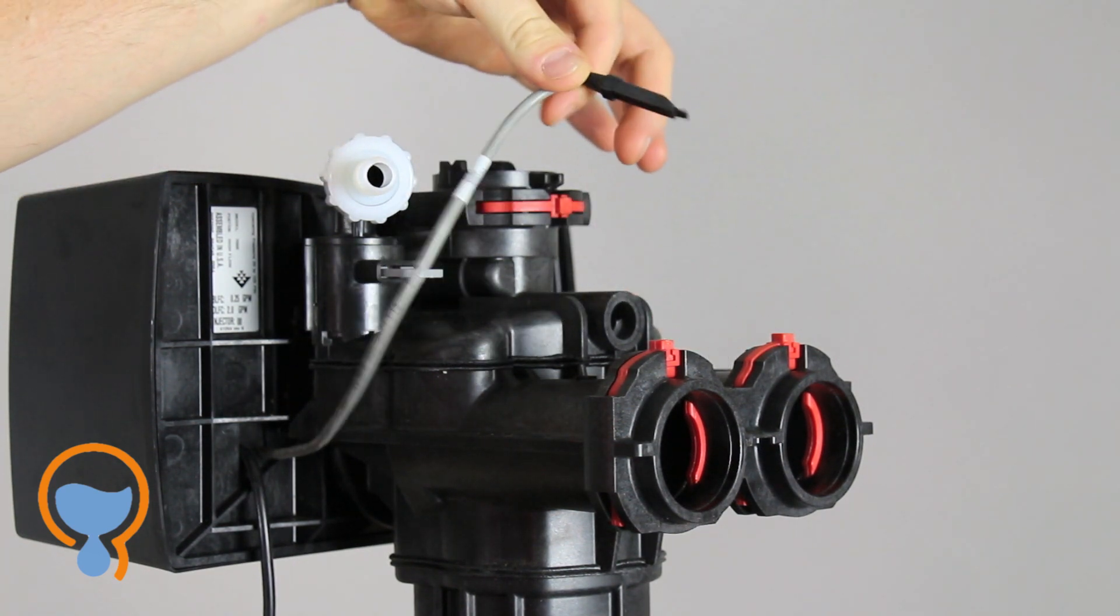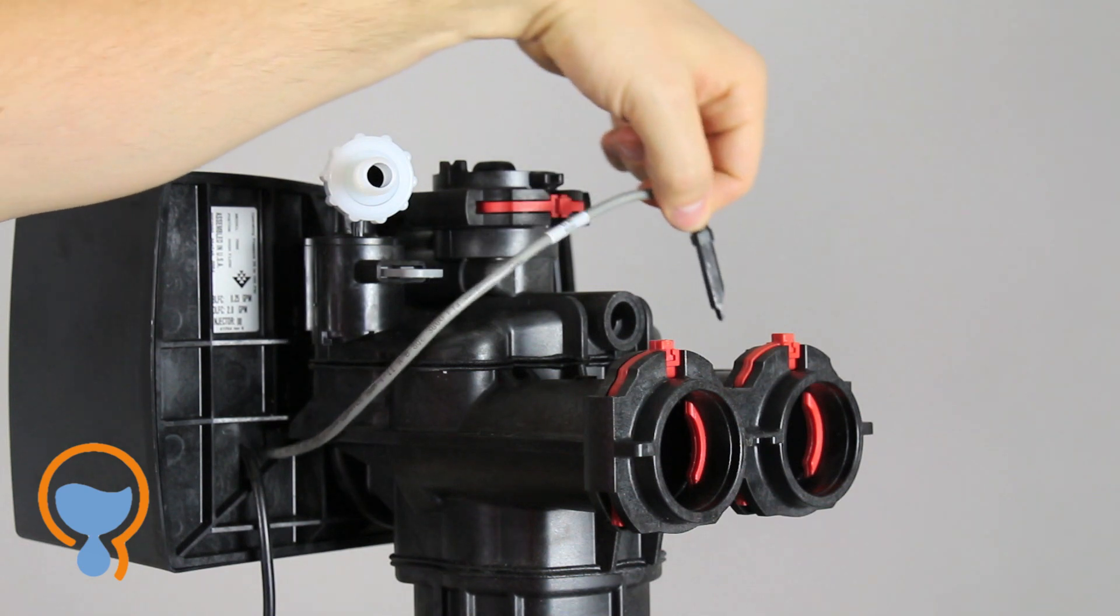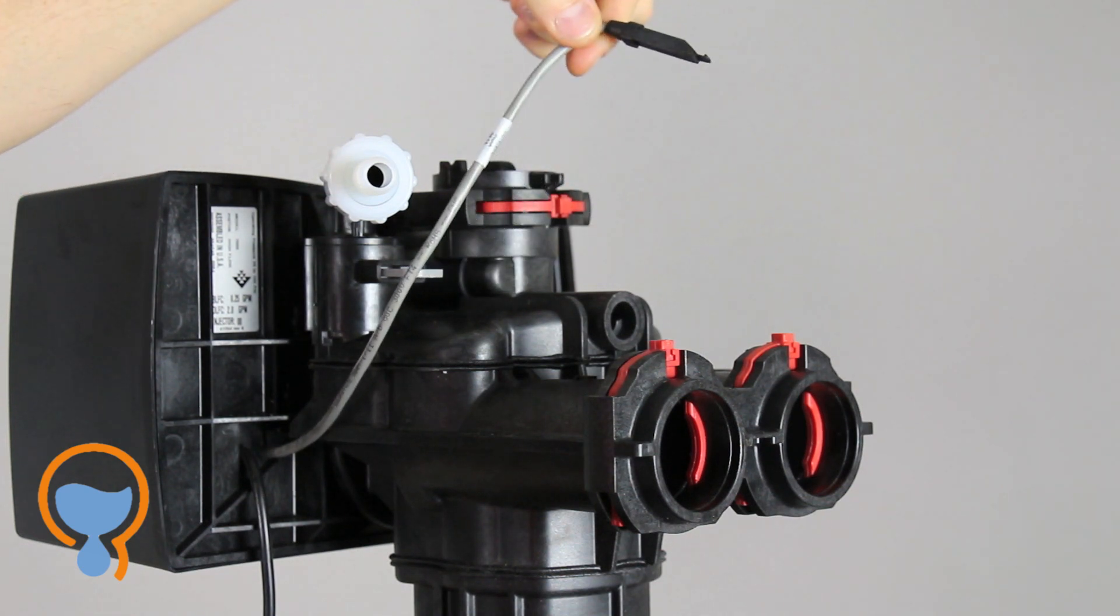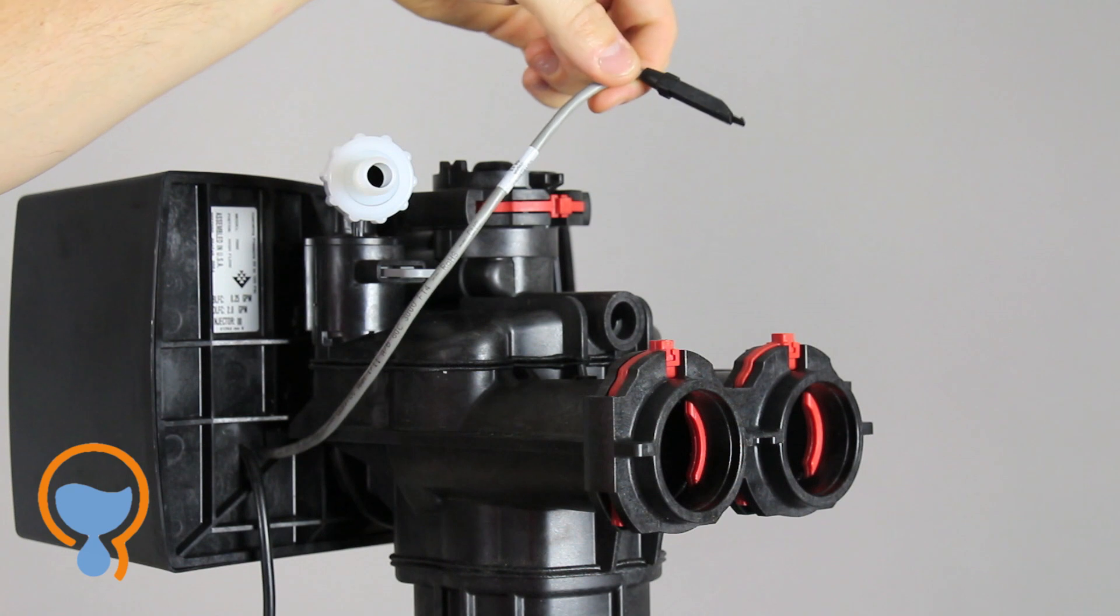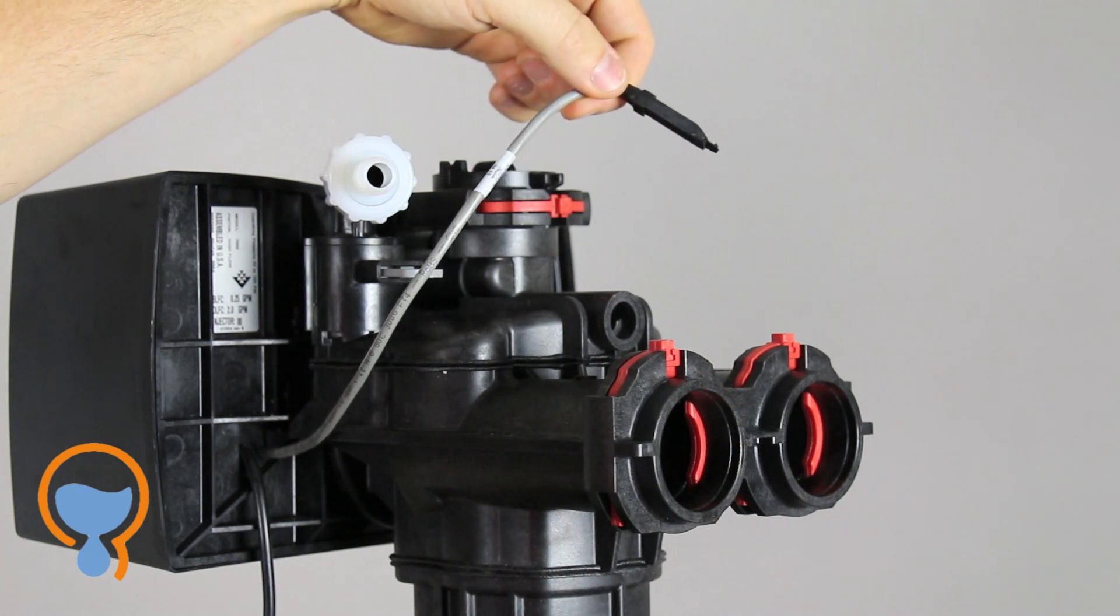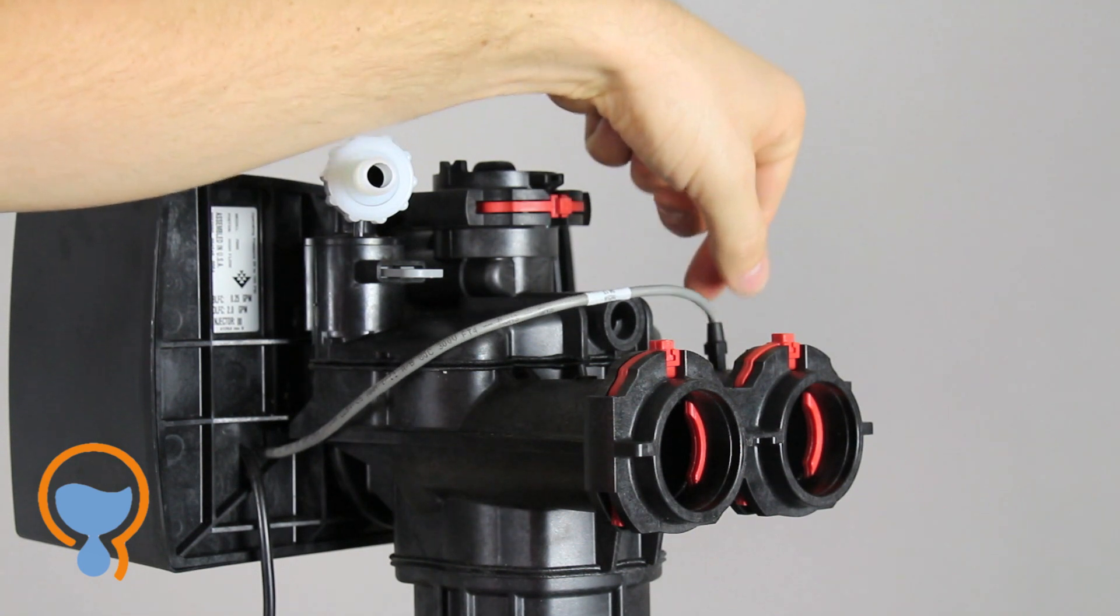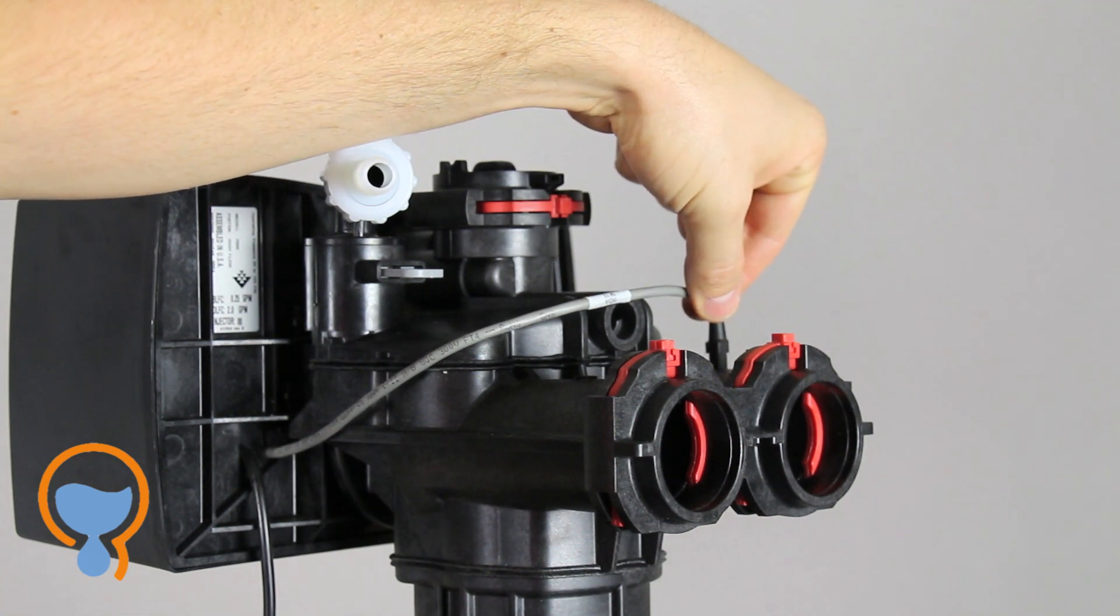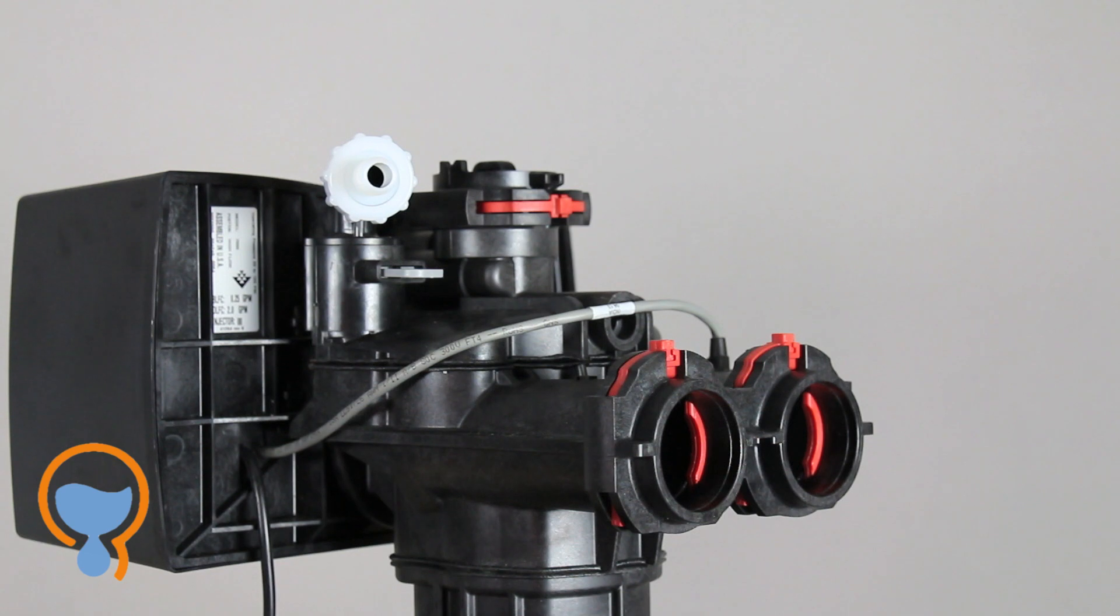A very common error that happens with the installation of these systems is this cable gets pulled out and the water softener control valve is never able to properly measure the water flow through the system, which causes all sorts of issues. So there's a little hole back here, there's only one way it can go in. Make sure it goes all the way in with an audible click and you know that you've got that seated properly and it's going to work well.